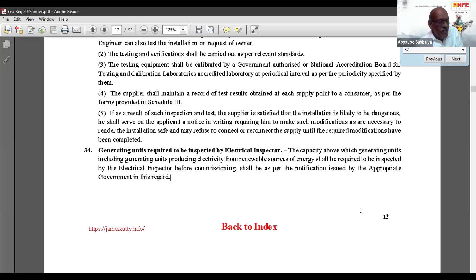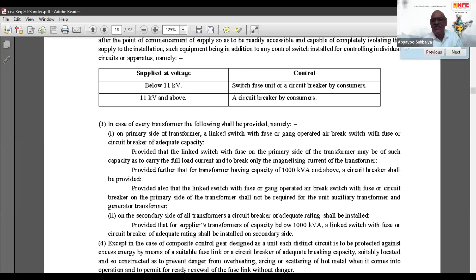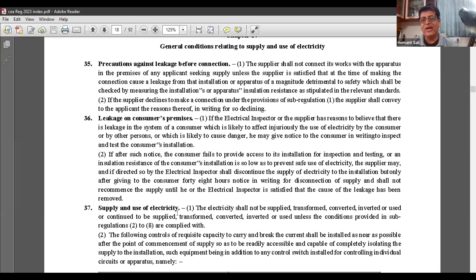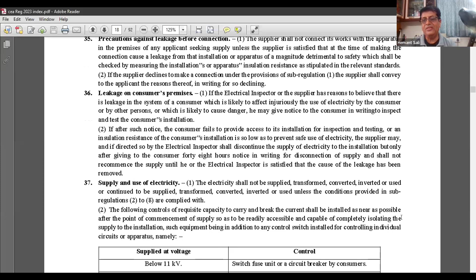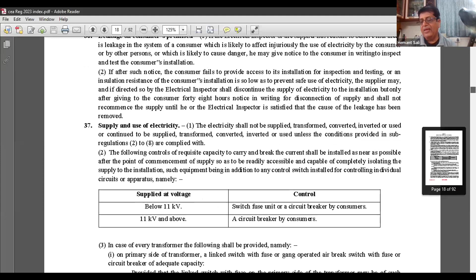We hope so. Then I will come again to you, sir, regarding regulation 37, because the breaker, it's a new point. Irrespective of the capacity of the transformer, there should be a breaker at the point of supply and use of energy. So recently the consumers ask whether I have to provide a breaker even for a 250 kVA transformer, etc. But any change will be tending towards the fine tuning of safety. What do you say about this specific provision, sir? Yes, sir. Previously it was relating to aggregate capacity. If it exceeds about 1000 kVA, then these things were applicable. Now, irrespective of capacity, they have set this condition to be complied at the point of supply.